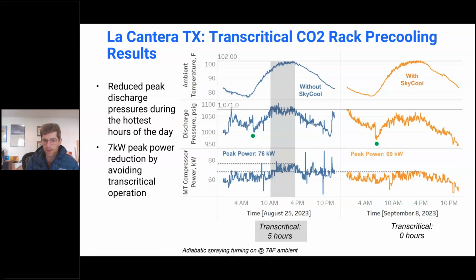over the summer. This is just 2 particular days with the panels on versus off, but you can see adding the panels lowered the discharge pressure relative to when the panels were off, and that had implications on power usage. And for these particular systems, they have some issues with control stability with CO2 systems as they transition from subcritical to transcritical, but we're able to prevent those issues from occurring.